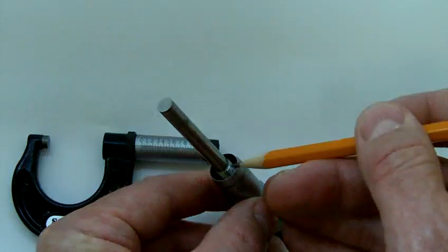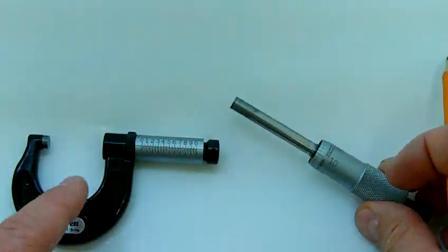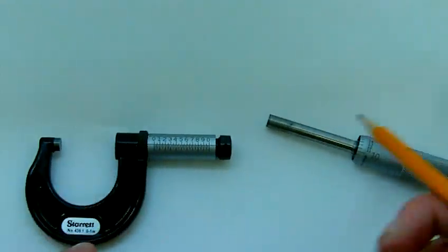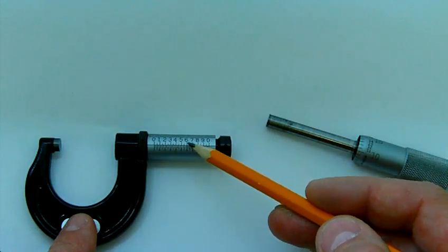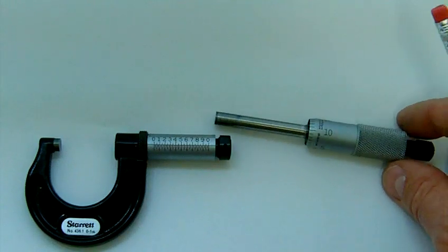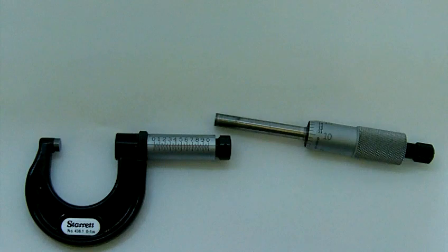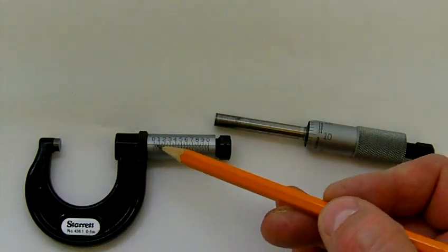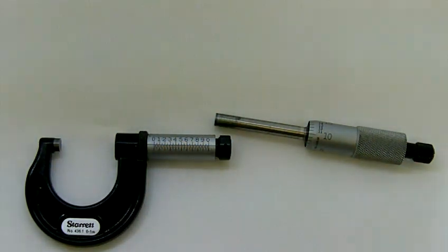40 threads to the inch. So if I give the thimble one complete revolution, it would move the micrometer one fortieth of an inch. If you take your calculator and put in one inch divided by 40 and hit enter, the number should be 0.025 or what we would call 25 thou. So each graduation on the main scale will equal 25 thou.